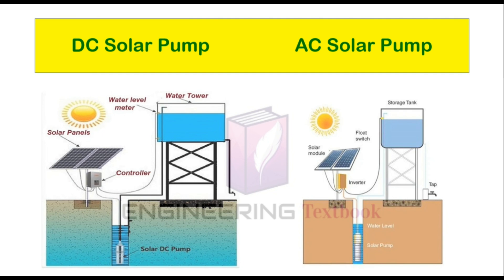In a DC solar pump, the pump has an electric motor that uses direct current. Therefore, no battery or inverter is required. Only the pump controller is attached after the solar panel and between the pump. In an AC solar pump, the electric motor works on alternating current. With the help of an inverter, the direct current produced by the solar panel is converted into alternating current. This conversion can lead to power loss during production and use.